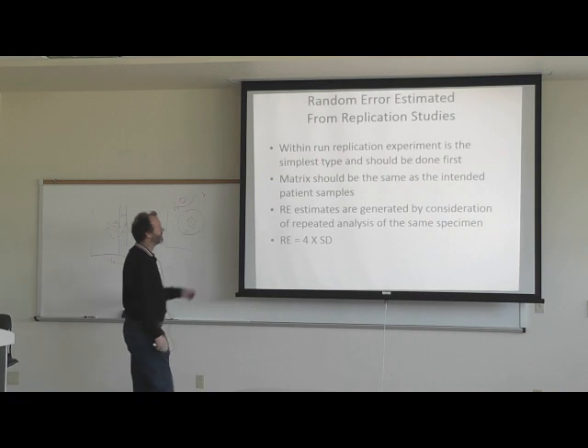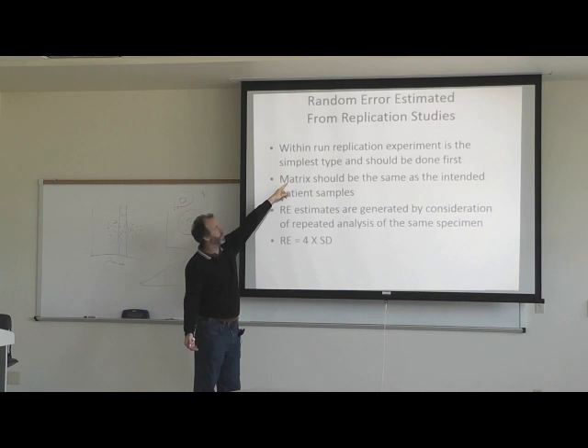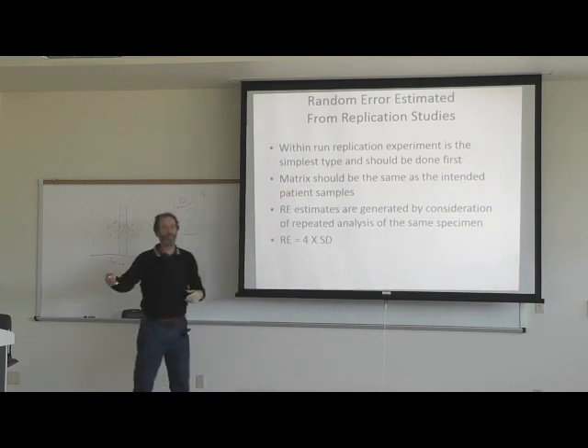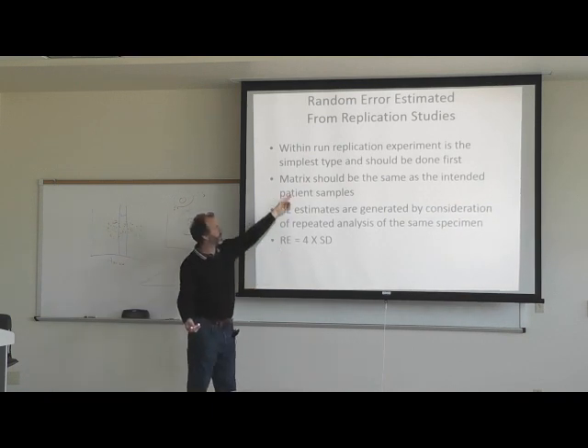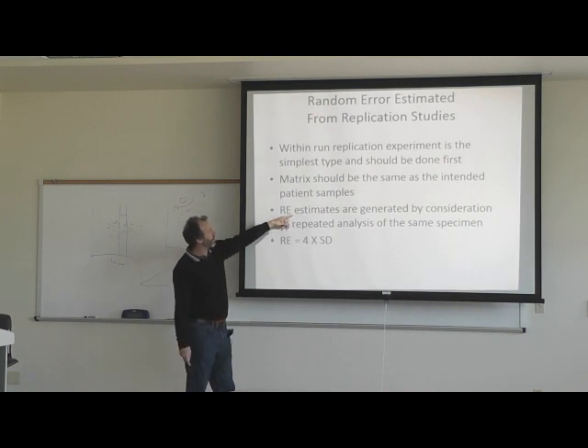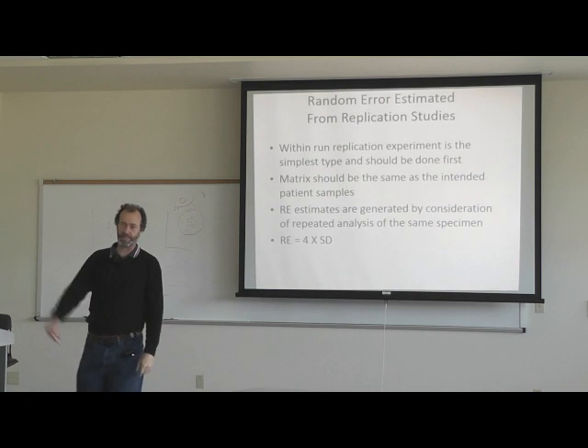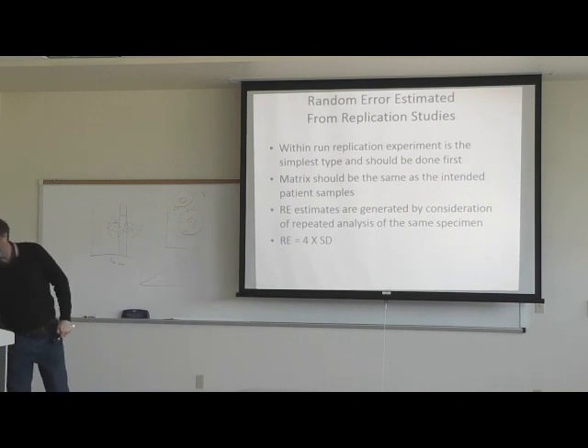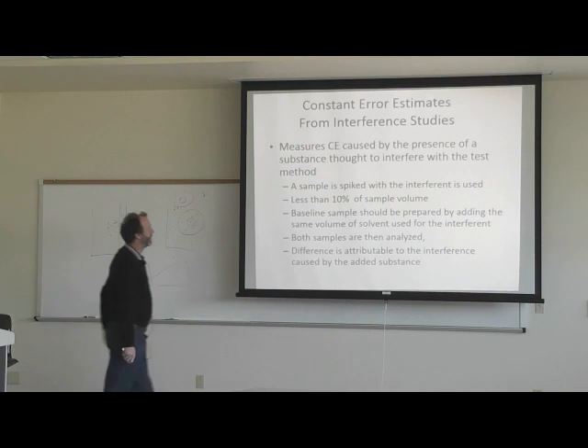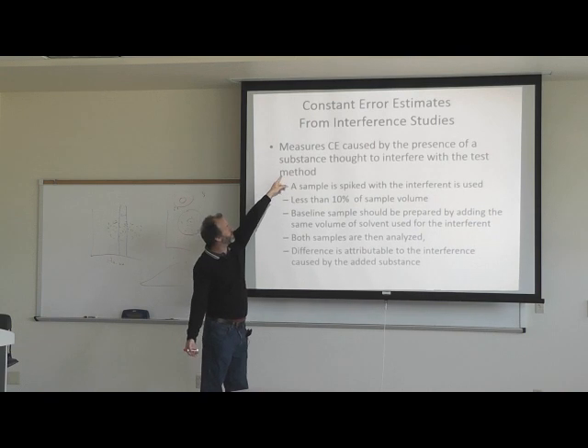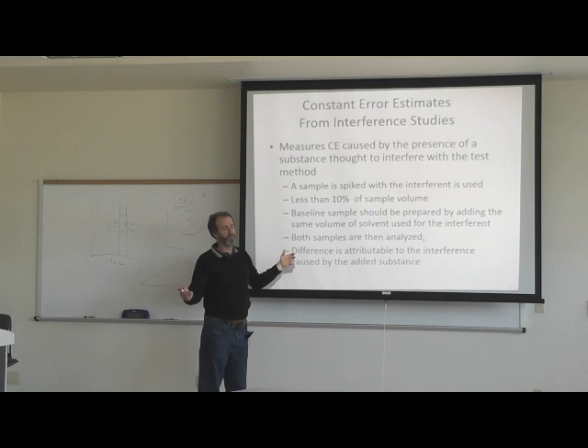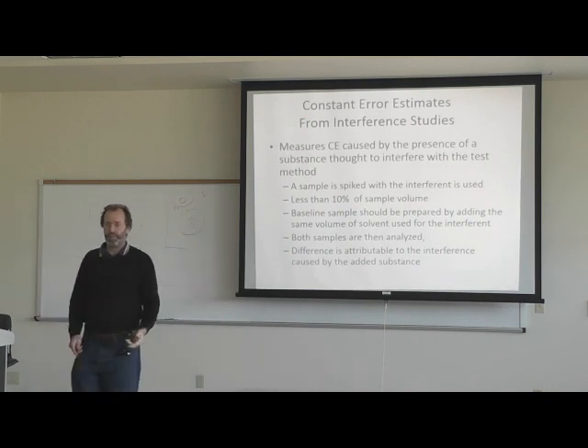Random error estimates from replication studies: within-run replication experiments are the simplest and should be done first. The matrix should be the same as the intended patient samples — if you're running serum, use serum. Random error estimates are generated by repeated analysis of the same specimen, and the estimate will be four times the standard deviation.